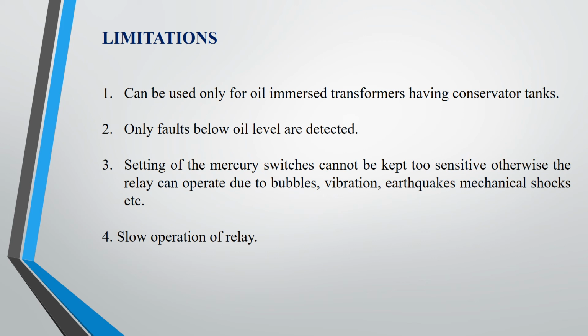Limitations of the Buchholz relay. This type of relay can only be used for oil-immersed transformers having conservator tanks. Only faults below the oil level are detected by the Buchholz relay. Also, the setting of the mercury switch is not kept very sensitive, as this can affect operation when bubble formation takes place, vibration is there, or earthquake and mechanical shocks occur.